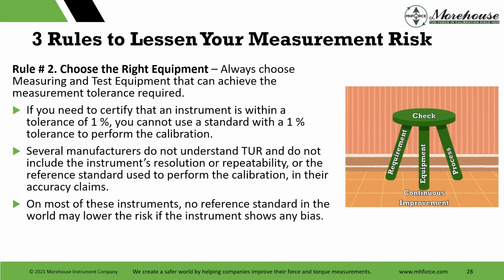I know something's good to 0.1%, but yet I'm measuring it with a device that's only good to 2%. Well, it doesn't matter. I don't need to report that. That's what we're talking about. And on most of these instruments, no reference standard in the world is going to lower the risk if there's any bias.